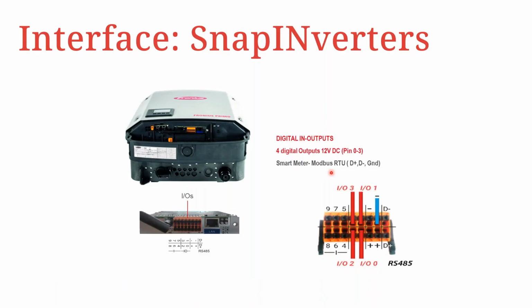When it comes to the wiring, specifically here looking at the Snap inverter, you have the same connection area where we do the connection for the smart meter. So you can see here to the right, bottom hand side, we have an orange plug where we have the connections for Modbus RS485. Within the same plug, we have the 4 outputs, which are position 0 up to 3. So we have 0 and then IO1, IO2, and IO3. So this can be used to control the 4 loads that I have just mentioned before.